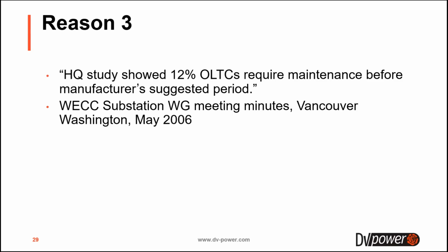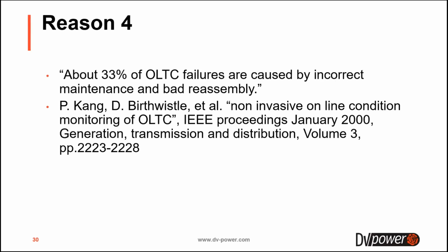The manufacturers of OLTCs will prescribe the suggested period for maintenance, either in numbers of operation or after several years, depending on which is shorter. But one study showed that 12% of OLTCs require maintenance even before the manufacturers suggest. So, okay, it is good to follow manufacturers' suggestions, but sometimes it's good to test OLTCs even more frequently than that. And the DVtest allows testing the OLTC in a very efficient and fast way.